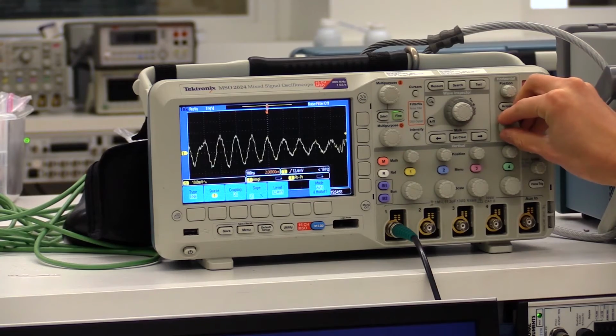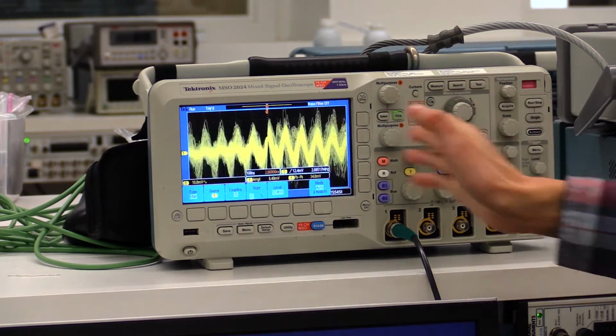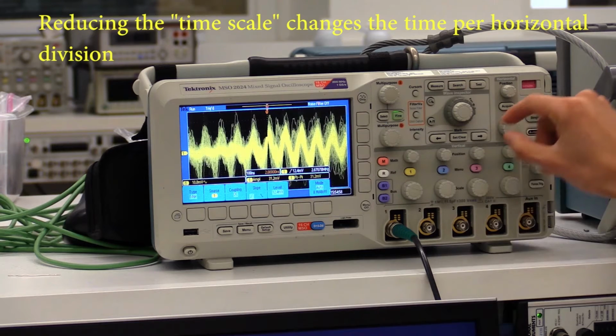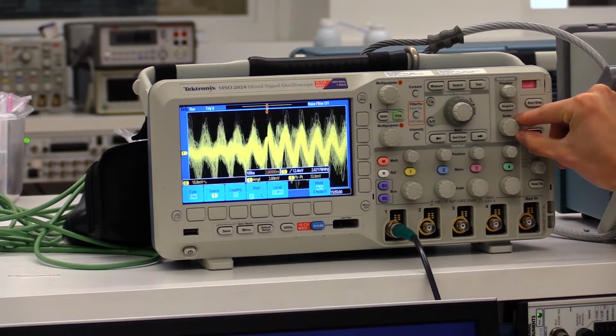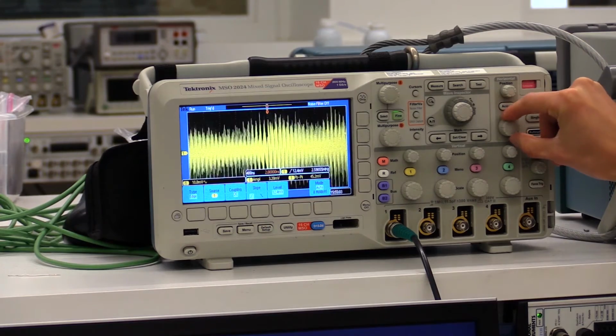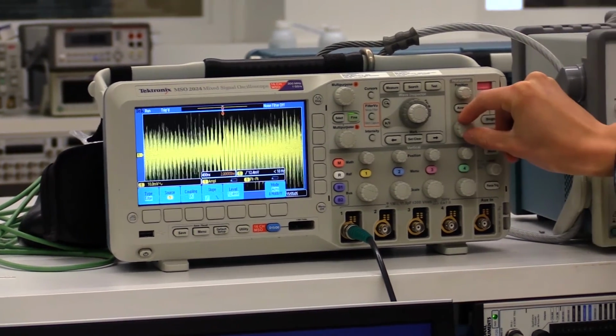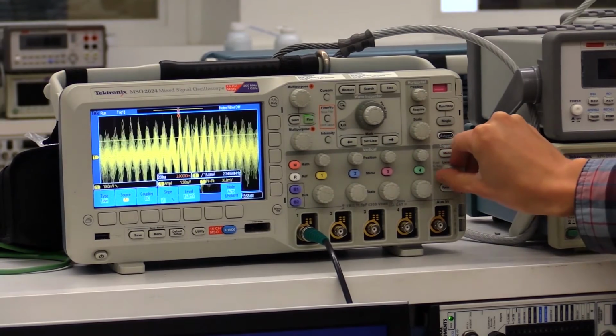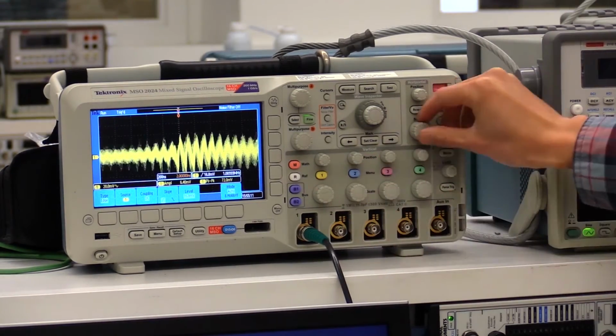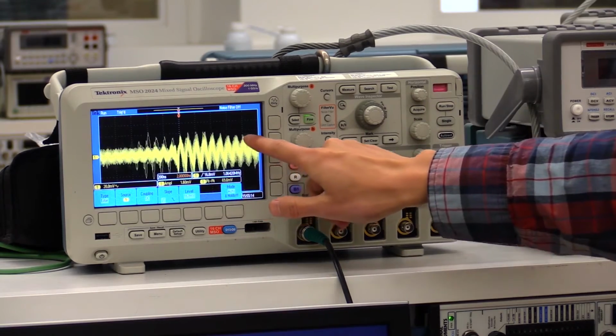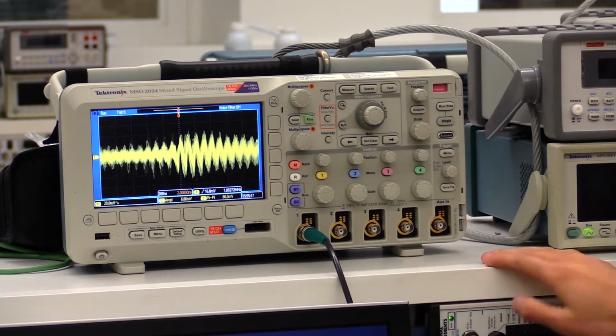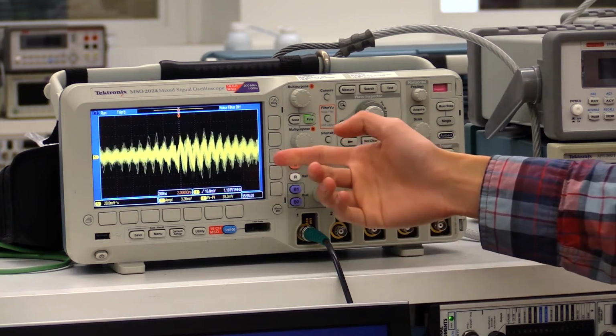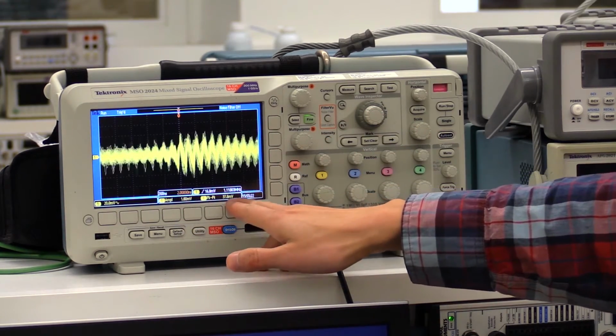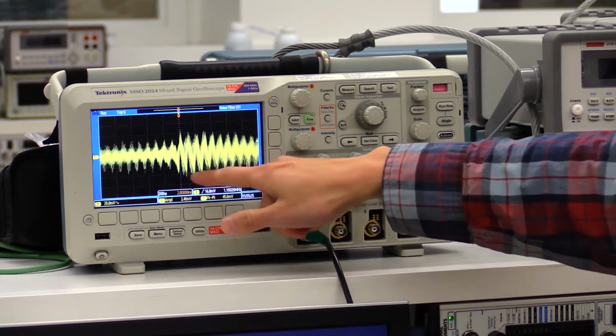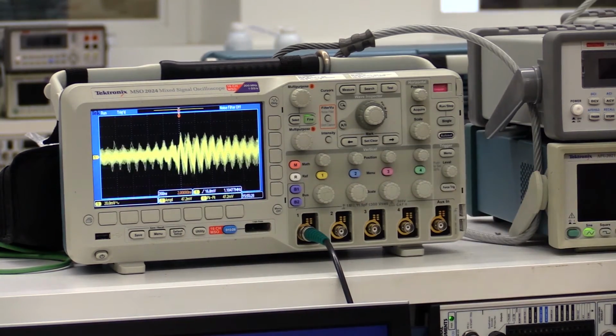So to get a better look at our signal, I'm going to reduce our time scale by adjusting this scale knob right here. And we see this signal. So this is the AC noise that's running on top of our DC signal, which is approximately around 60 millivolts, and we're measuring from here to here. So if you measure your signal later on, that kind of gives you an error bar.